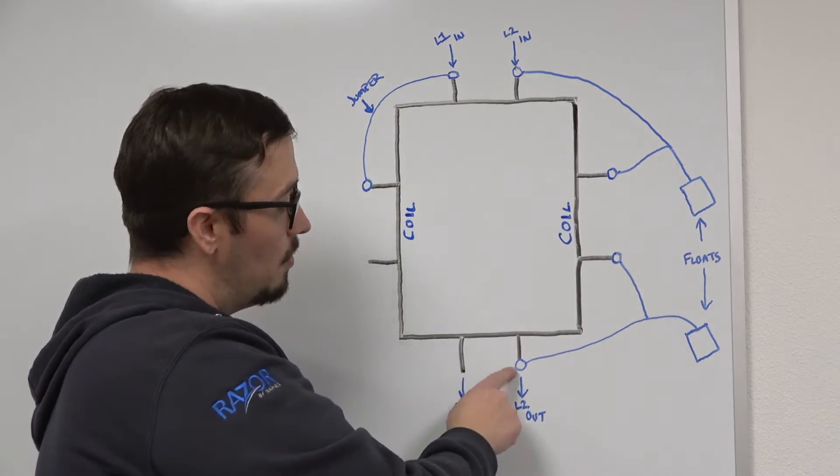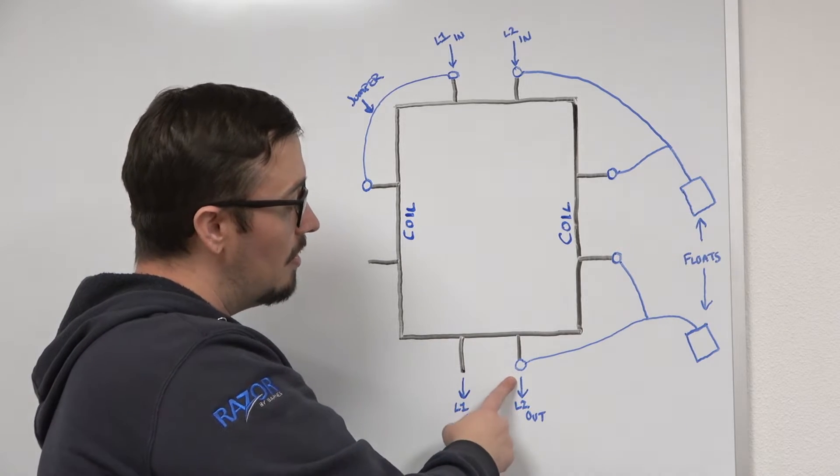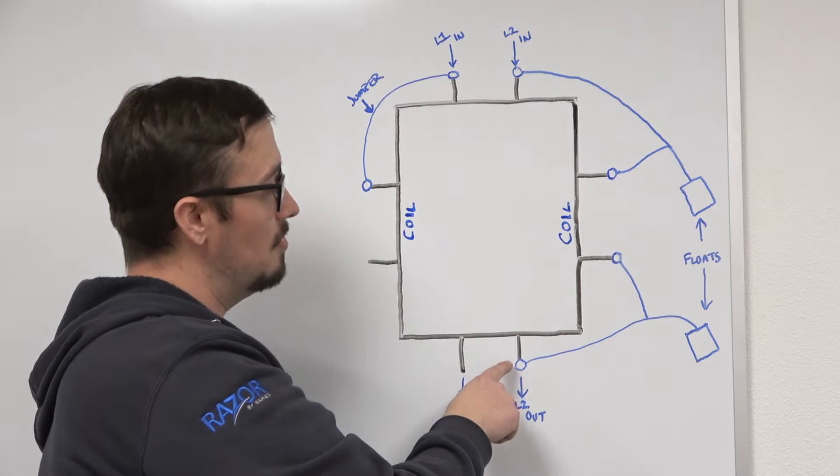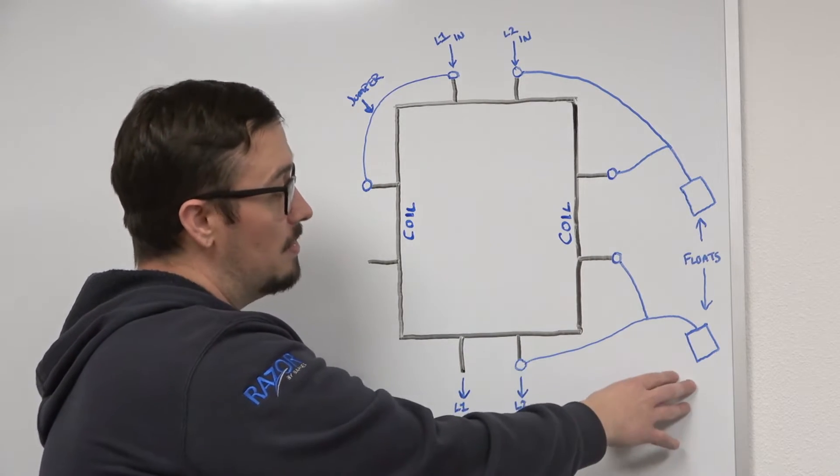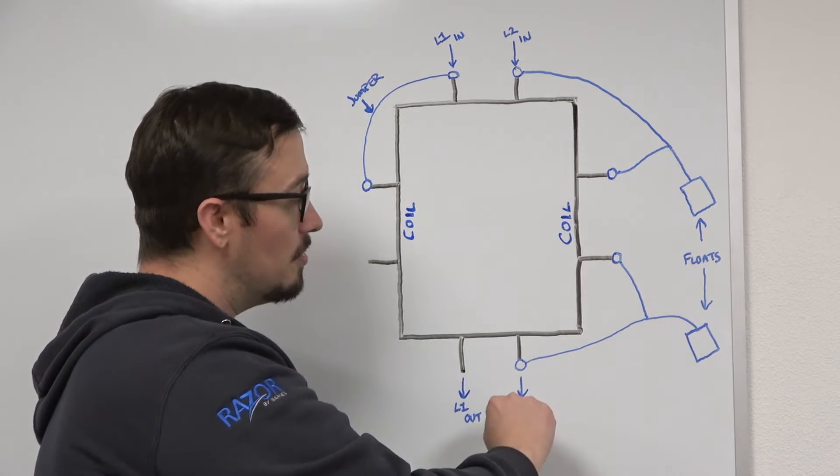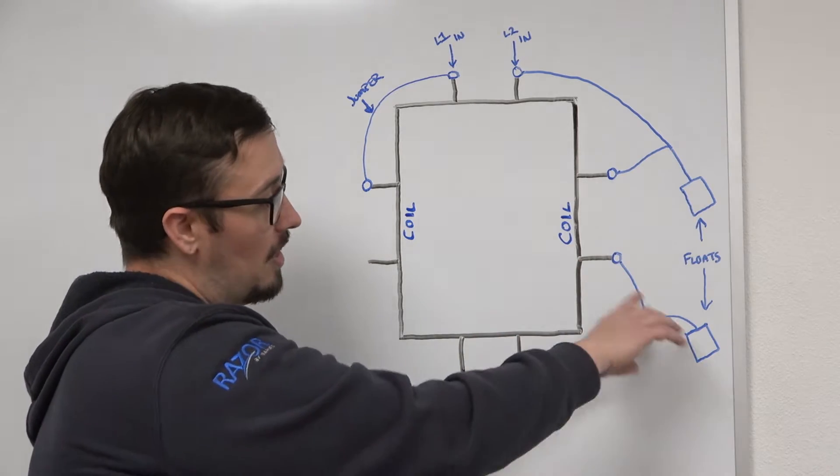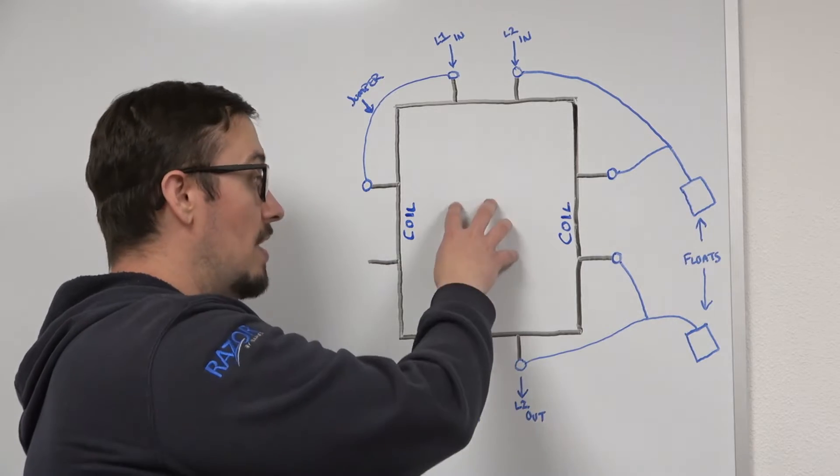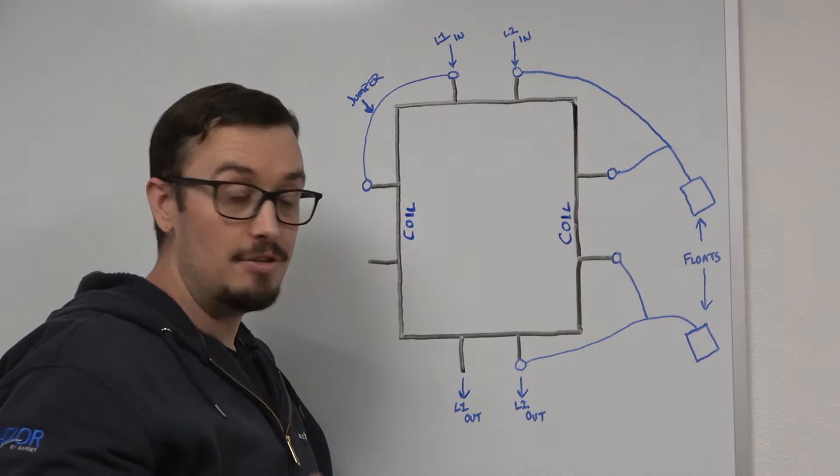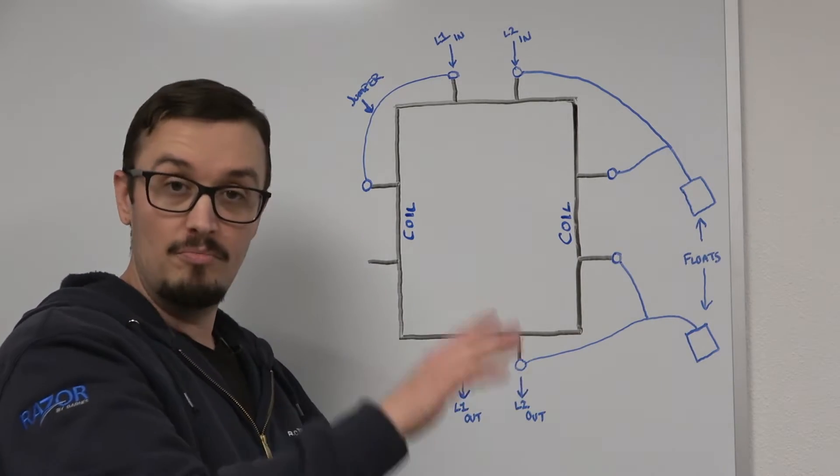As the contactor coil closes and sends energy through to this leg, this switch is actually what allows the power to be jumpered over to the coil from the pass-through side. This basically creates that holding circuit and keeps that relay or contactor engaged during the operation of both float switches.